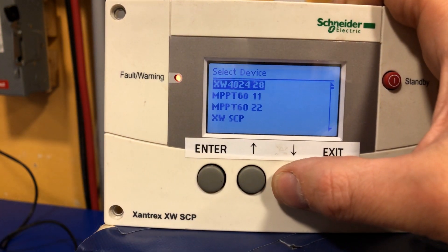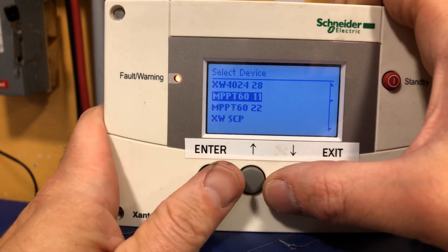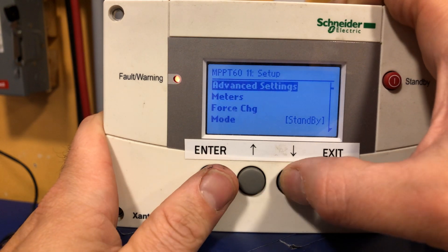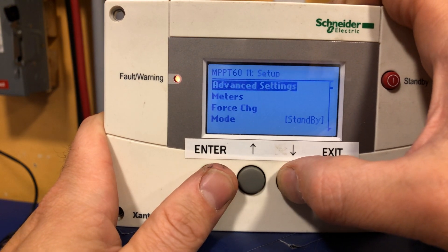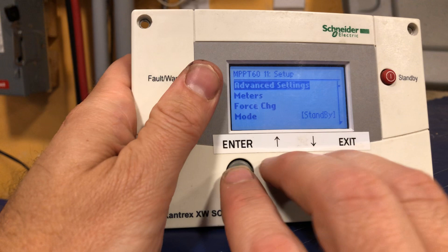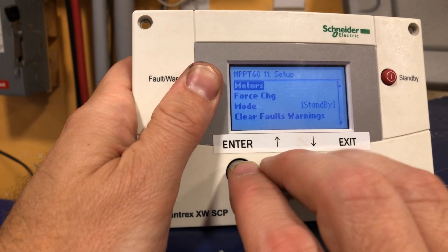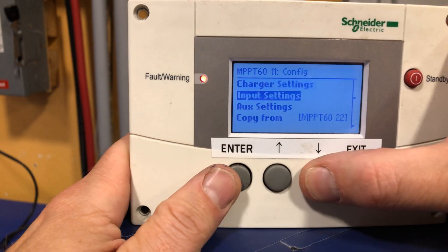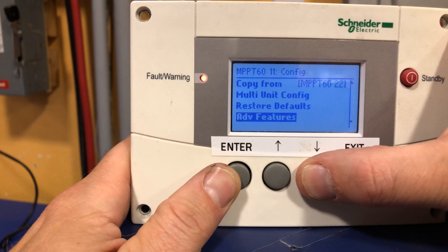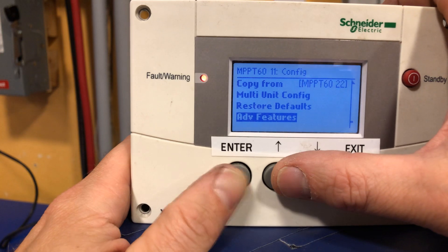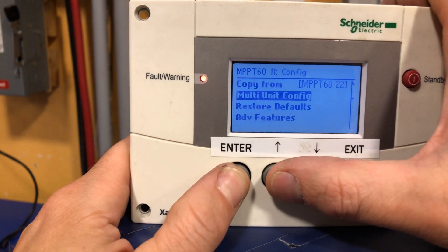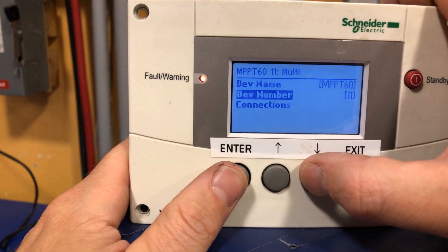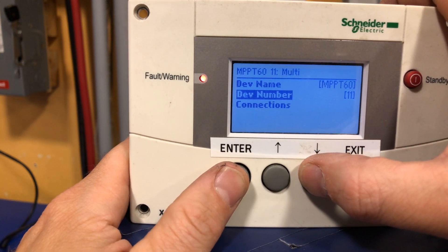We can see the MPPT60 charge controller — the charge controller is currently unit number 11. Press enter. Advanced settings is already there from the three-button press. Let's go into multi-unit config. Device name — don't press enter here, press down. Device number.